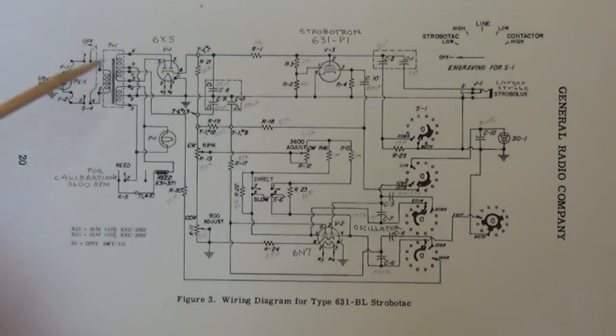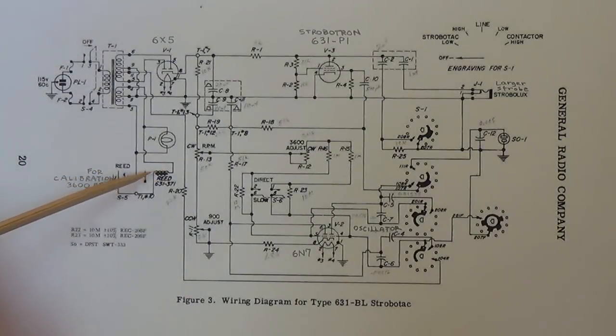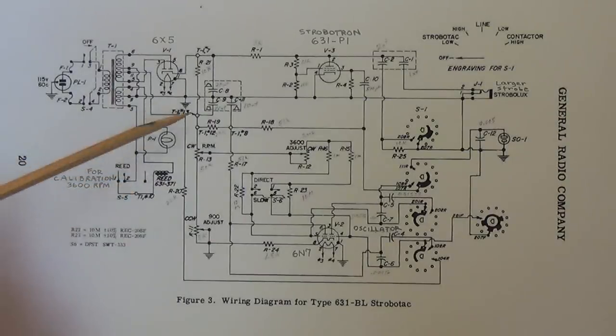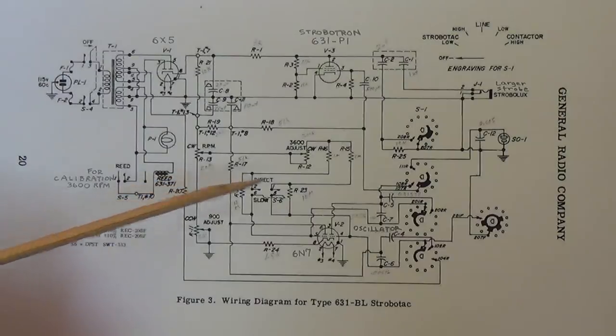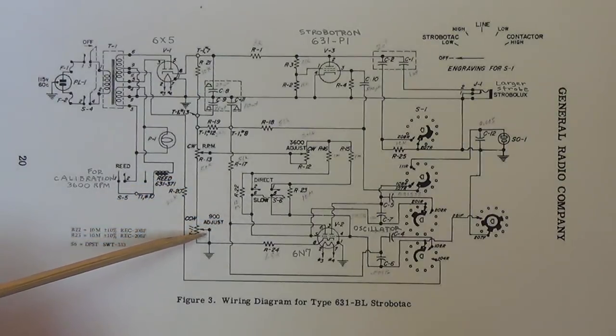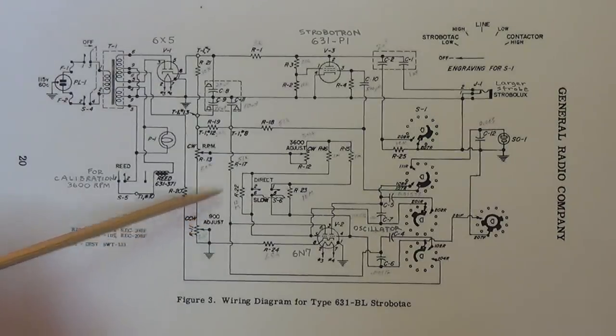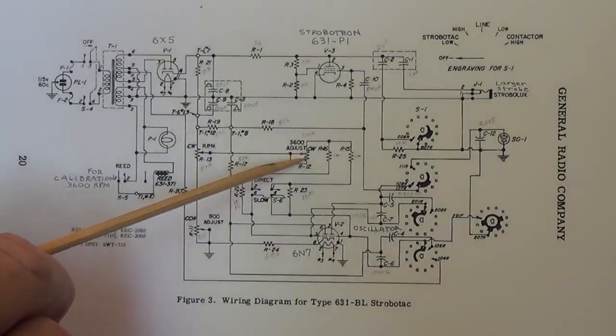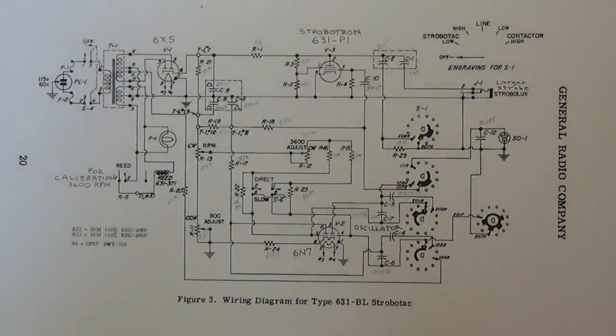A few other little tidbits. We look over here and see the electromagnet for the reed, and that it is pre-rectifier because we want AC at 60 cycles per second to operate the leaf and make it wiggle so that we can use it for calibration purposes. Here is that Mazda bulb that lies underneath our calibration readout wheels to backlight them. And I guess a couple other things. When we adjust the calibration of the device, this is the potentiometer for the 900 range, and this is the potentiometer for the 3600 range.